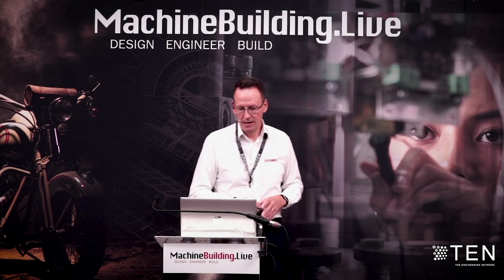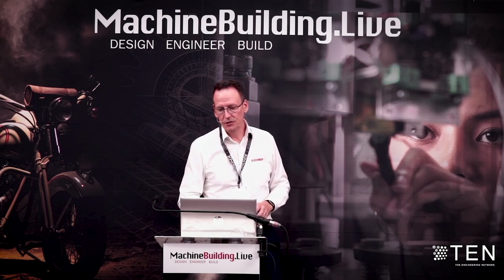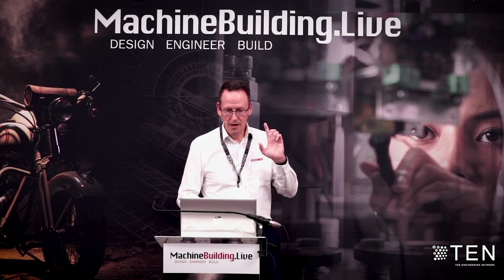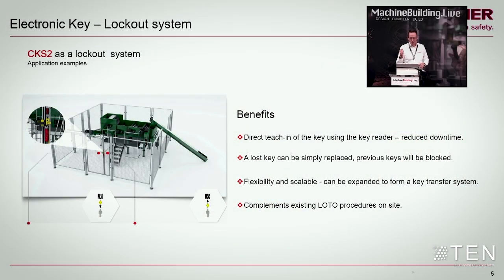As a lockout system, we have a main key, which we use in conjunction with maybe lockout, tagout regimes on site. It's directly taught into a specific key reader. If you lose that, you can quickly and easily program another key because it's electronic. We can do that through the reader. There's a little button on the back to do a teach facility. There's a specific procedure to do that, which makes it a bit more robust.